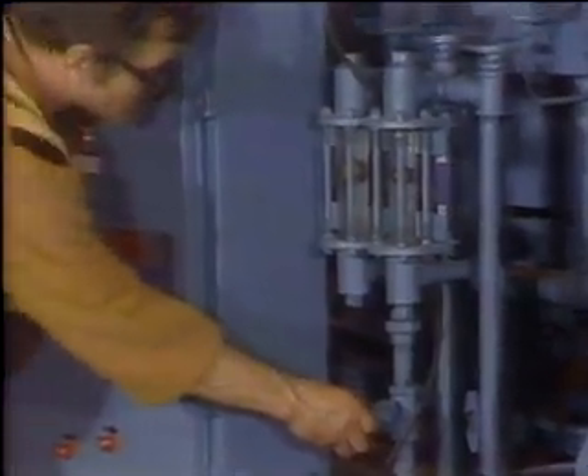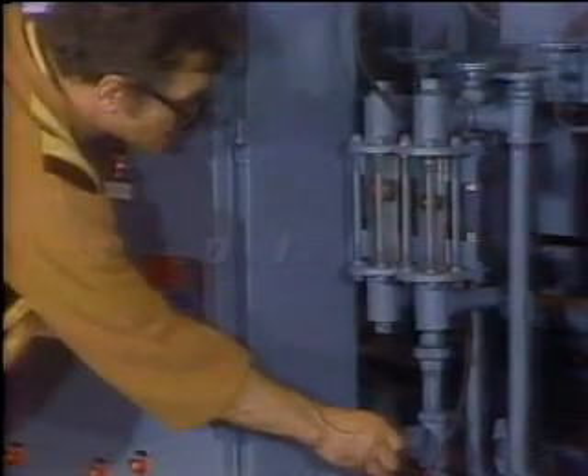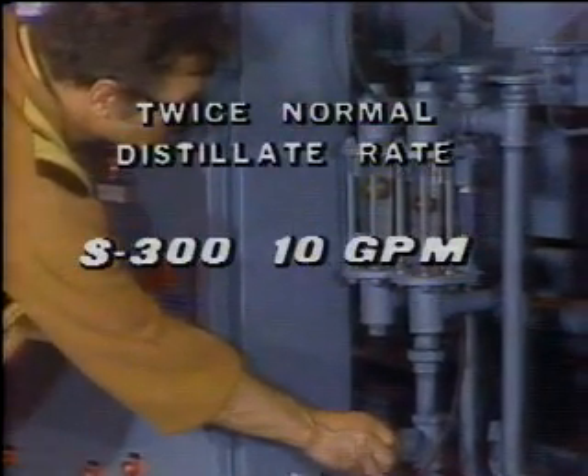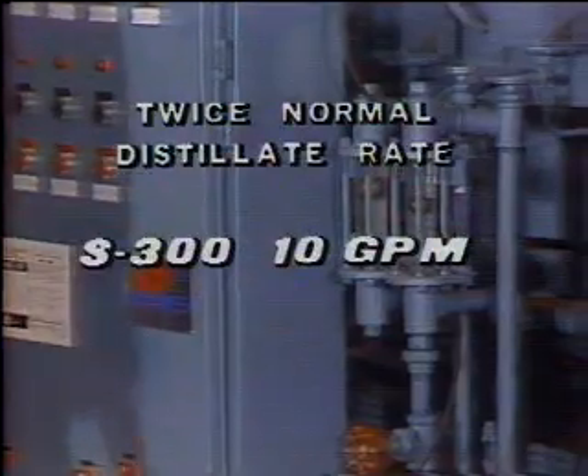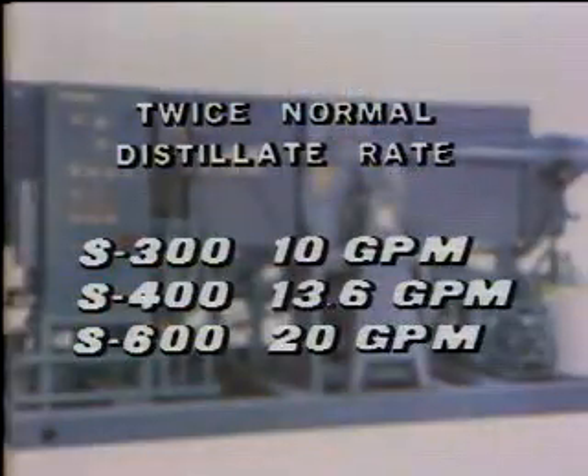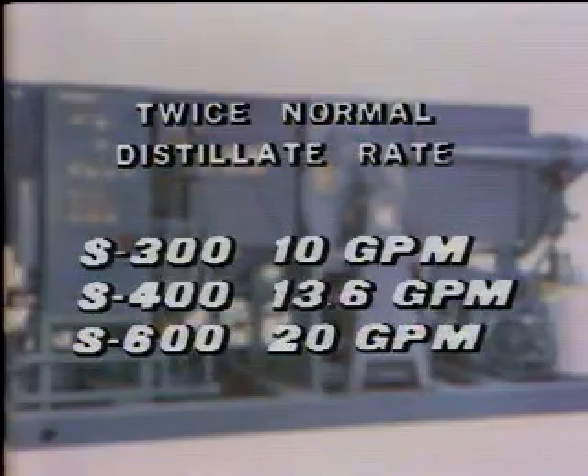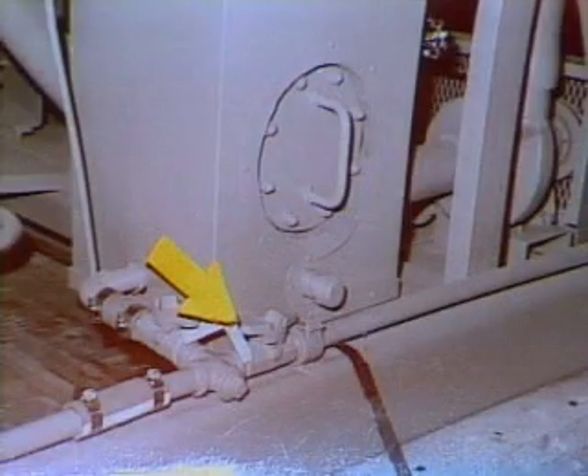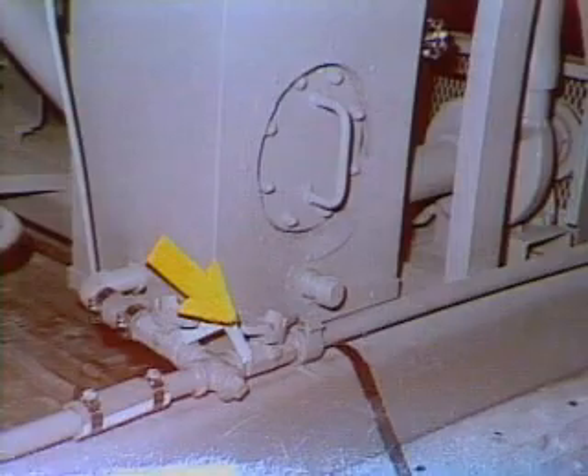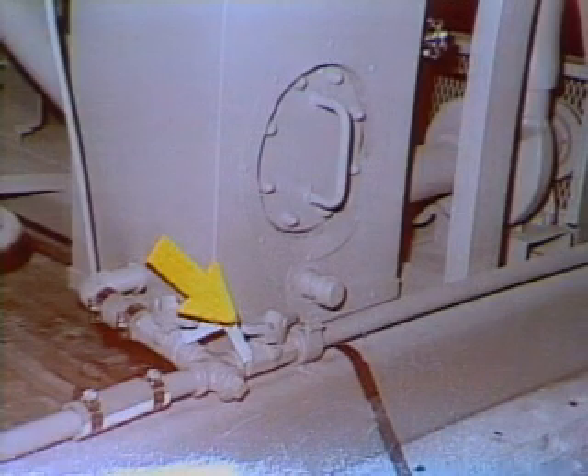Now, open the feed water control valve slowly to twice the normal distillate rate. That'll be 10 gallons per minute on this 300 series, 13.6 GPM on the 400 series, and 20 GPM on the 600 series. When the sump level rises to within 3 inches of the top of the gauge glass, open the blowdown shutoff valve here. This will carry off the impurities left behind after distillation has taken place.